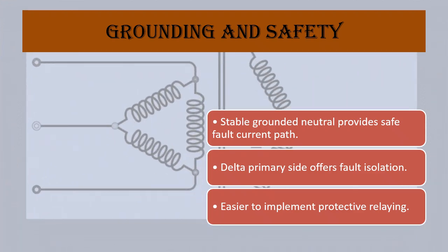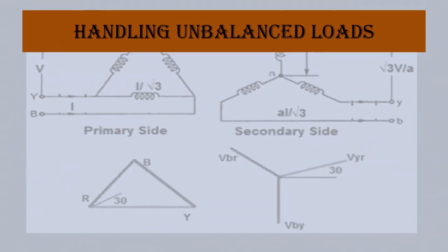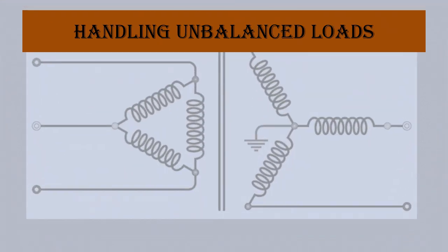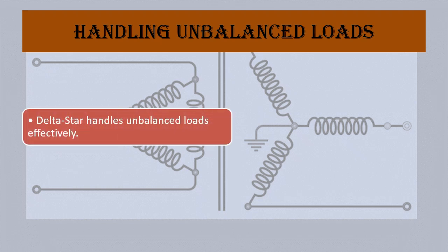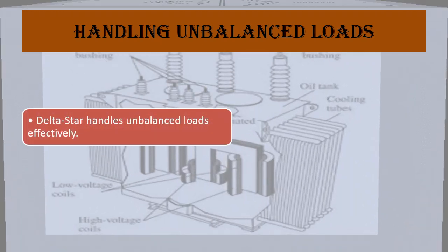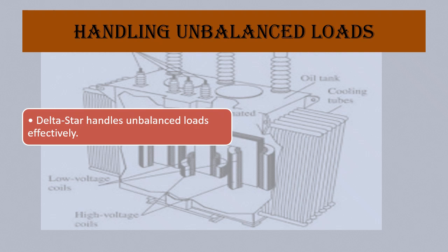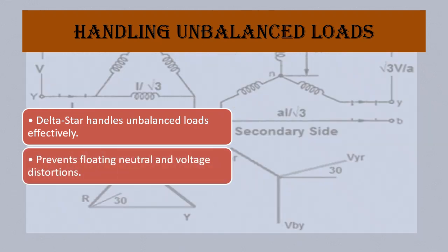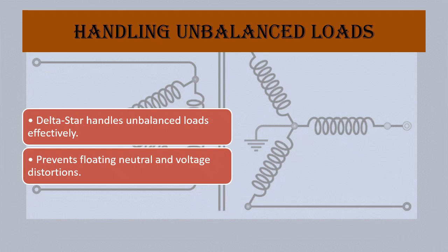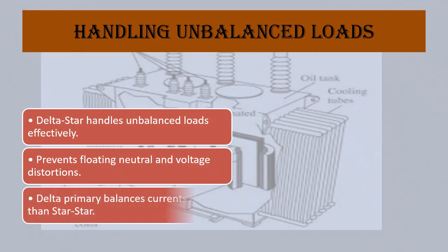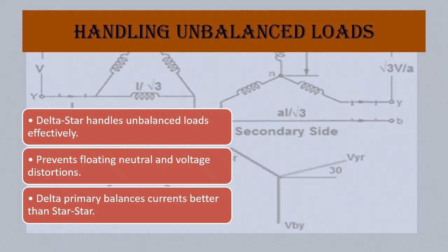Handling unbalanced loads. In real-world distribution systems, power demand is rarely balanced across all three phases. Delta-Star transformers handle these unbalanced loads effectively. The delta connection on the primary helps balance currents, preventing issues such as voltage distortions or floating neutrals that might occur in other configurations.